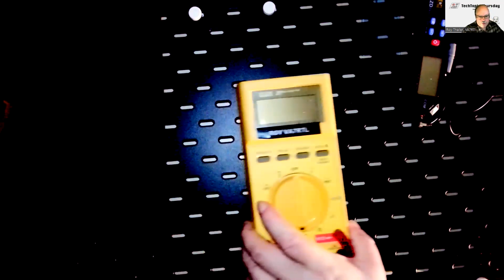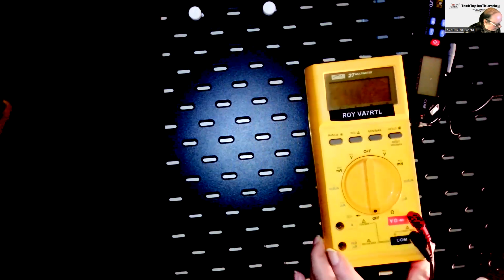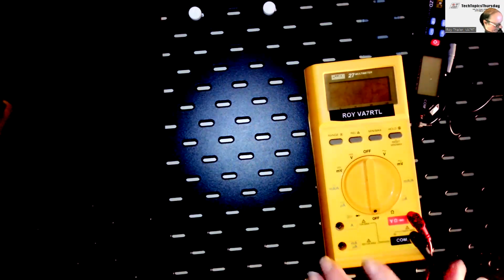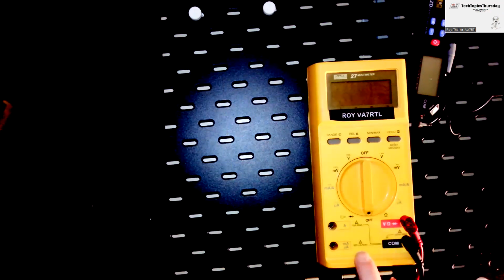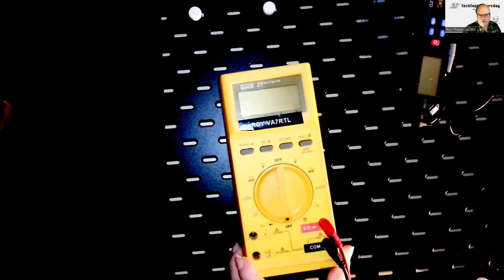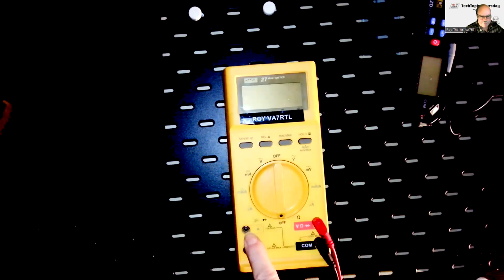Now this is the Fluke meter. It doesn't have the category listed on it, but if you go to the website, it's got a 320 milliamp fuse and a 10 amp fuse, but it doesn't say anything about rating. So I checked the manufacturer's specification, and it's 10 amp continuous. So I can leave this hooked up to anything up to 10 amps and it won't burn out. It's a little different in that you have different settings for current: milliamp and microamp are measured here, and amps are measured here.